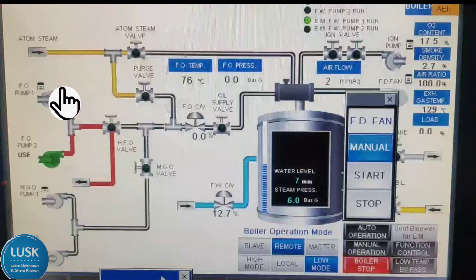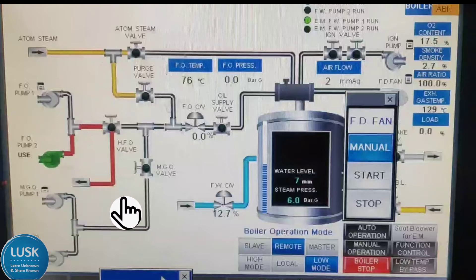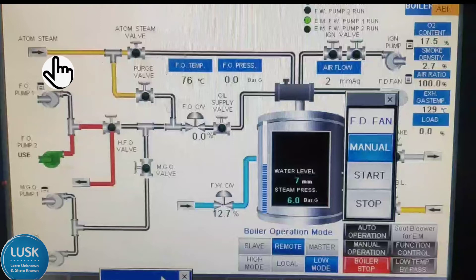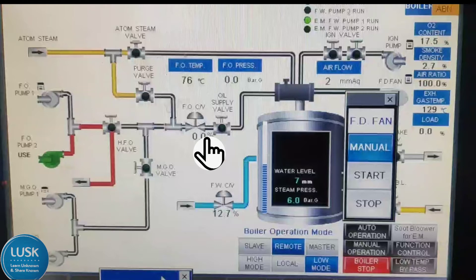Here you can see there are 4 pumps: fuel oil pump 1, 2, and MGO pump 1, 2. MGO is nothing but marine gas oil. Any one pump only you are going to use at a time, according to the requirement. The red indication is the fuel oil indication, and this yellow indication is atomizing steam. Atomizing steam is used so that when fuel goes through the nozzle, atomizing steam also goes at the same time, forming a mist or cloud inside the boiler, so the firing will be good.